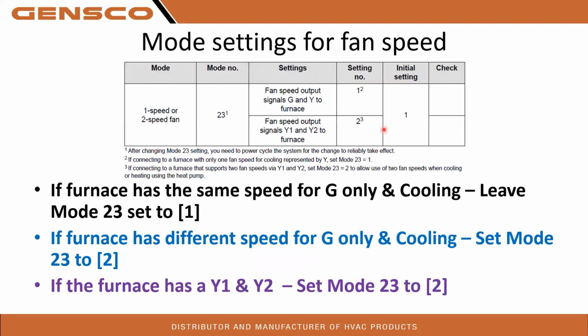Mode settings for the fan speed. So one thing that you guys are going to be aware of is when you're programming your thermostats or your dip switches, what's in your MHK2 manuals and stuff is going to be a little bit different in Intelli-Heat. They're going to have some different meanings in there. So you're going to want to make sure to read your manuals to make sure you're setting these things up correctly. If you're used to just your standard setups, you may end up having some issues with this.